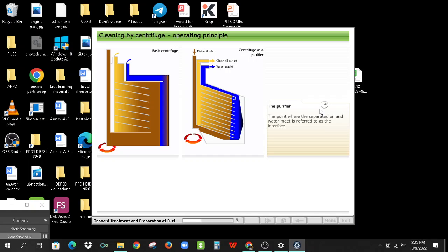The point where the separated oil and water meet is referred to as the interface. The position of the interface is controlled by using gravity discs with different size central holes or gravity plugs of different length. These determine the effective position of the water outlet. The clean oil passes up the outside of the central tube to the outlet to the service tank. The water flows over the disc stack cover plate to the edge of the gravity disc or plug and out through the water outlet.